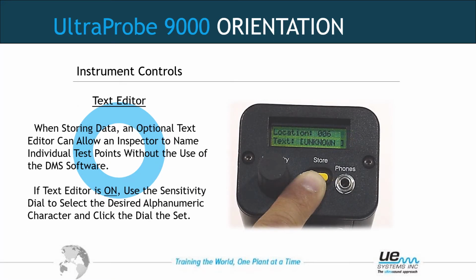Hit the storage button one more time and you get location 006 and the text unknown. This unit will show you part of the route information. So if we had named this particular test position motor 1 inboard bearing, motor 1 would be the machine or location from the DMS software, and inboard bearing would be the actual test spot. This would show us motor 1, the location or machine name. It does not show the test point name. So motor 1 at record number 6.